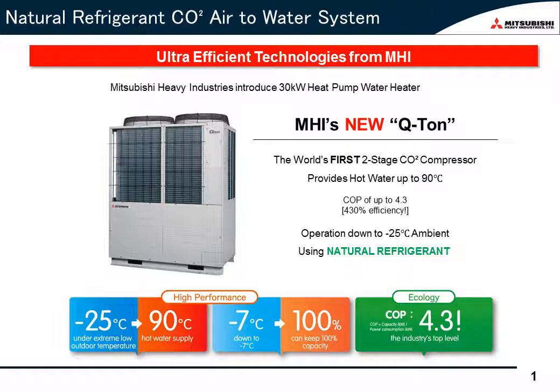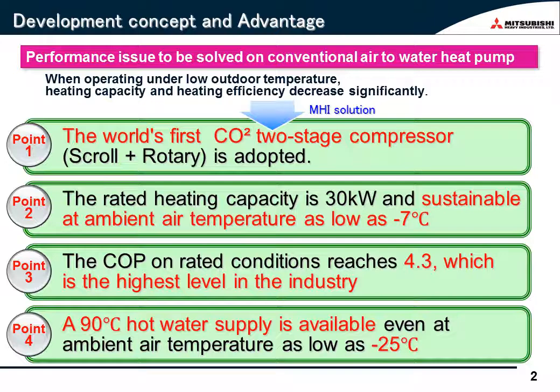The rated heating capacity is 30 kilowatts per hour. That means it has the ability to make three tons of 90 degrees Celsius hot water in eight hours. The conventional EcoCute had some problems that are specific to the air source heat pump — when operating under low ambient temperatures, heating capacity and heating efficiency decreased significantly. In other words, conventional EcoCute had difficulty in making sufficient hot water during winter. That was the major problem compared to the boiler system. Q-Ton was developed to solve the problem of heat capacity and heat efficiency dropping.